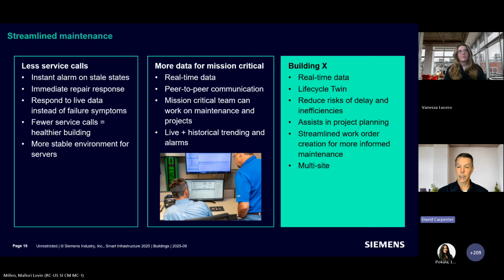In Building X, you're seeing every change of value—temperature, analog outs, analog ins—so every bit of information is captured. We're able to analyze it and determine if PIDs need tuning, or if there's a problem with fans or valves that will cause physical failure sooner than expected. It also allows for multi-site viewing for facilities distributed all over the United States, or the world.